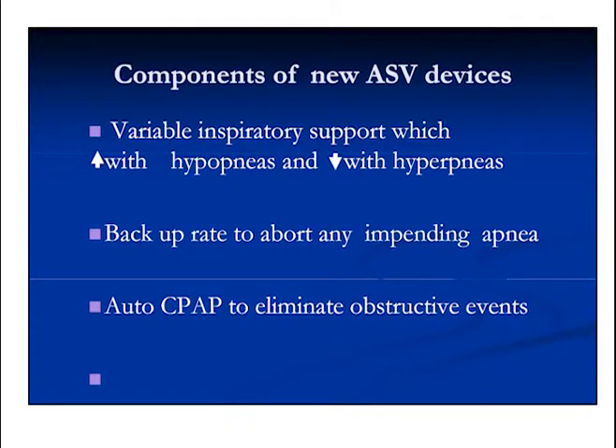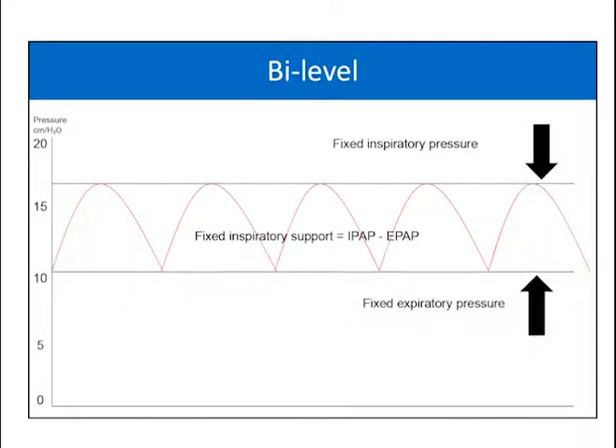These ASV devices have variable inspiratory pressure support—we'll talk about that in a moment—a backup rate, and auto CPAP. The auto CPAP eliminates obstructive events, the backup rate activates if there's an impending apnea, and then there's the variable inspiratory pressure support. Remember, inspiratory pressure support, at a high level, is the pressure difference between inspiration and expiration. So in this case, say 16 here, 10 here, the pressure support is about 6 centimeters of water—fixed inspiratory pressure support with bilevel.